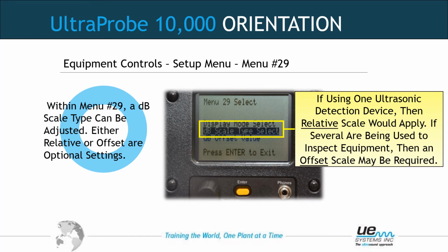More typical would be you would offset the 401 grease caddy by a +8. The offset values have a wider range on the 401 grease caddy. So for dB scale type select, you have relative or you have offset. Relative is relative to UE's calibration. Offset is for the instance that I just described to you. We never offset the unit if it's out of calibration. Offsetting a unit for a poorly calibrated unit does not help. Only between units do we offset.